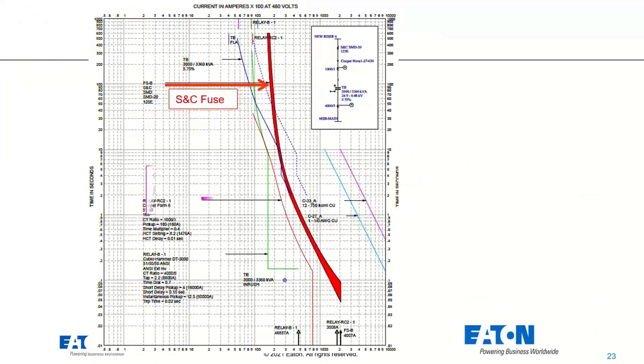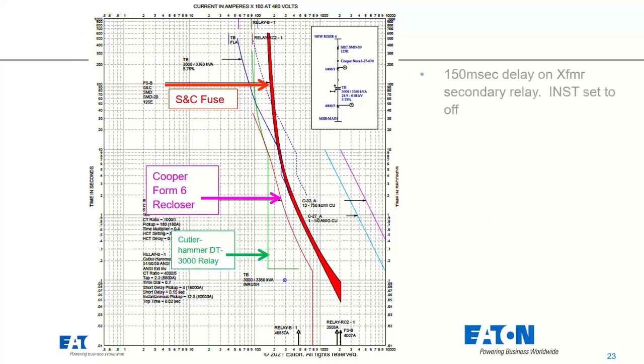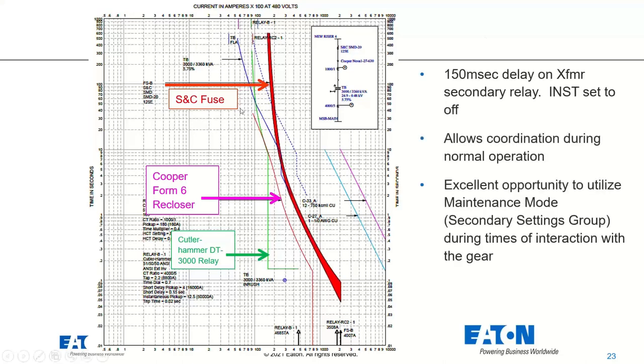So another case study here that I want to show is the TCC for the previous design that we just had, showing you the coordination, really. This S&C fuse is what's feeding upstream of the recloser. Then the recloser curve itself, and where we can be with the secondary relay. And now transformer inrush, down here, the small blue dot. Typically we're going to have that recloser relay set to get around that inrush value so we're not nuisance tripping on startup, but it's going to create a longer duration as opposed to something like an instantaneous or 51 setting on the secondary relay that can react quite a bit faster.